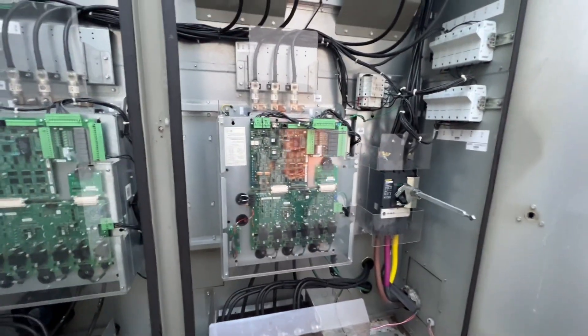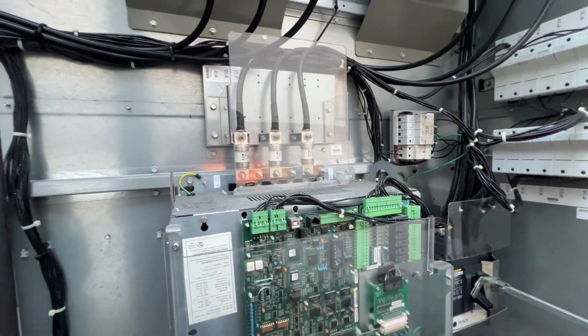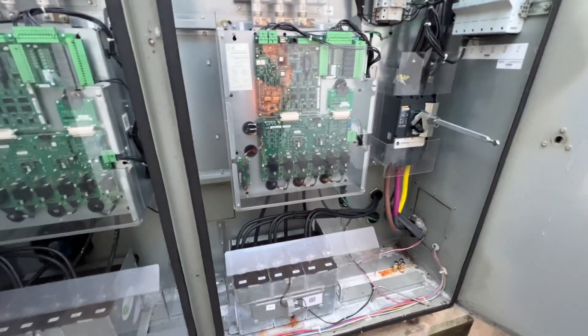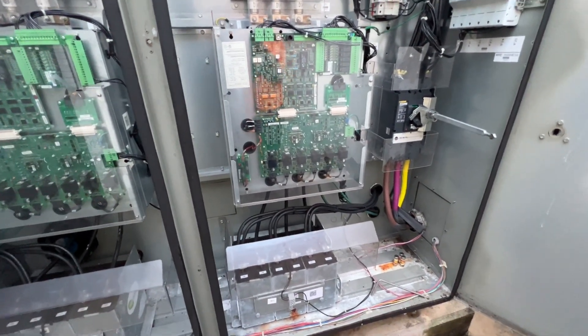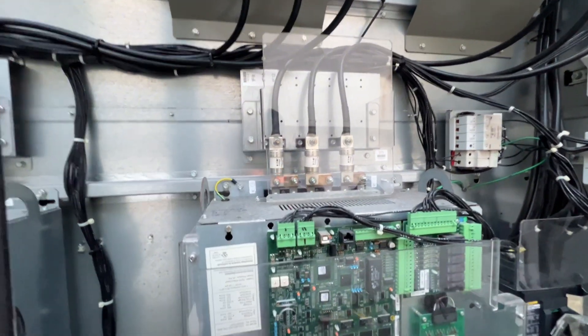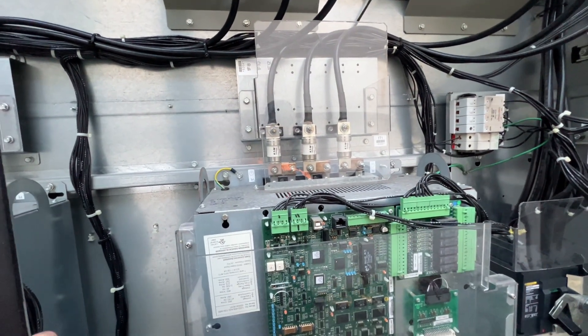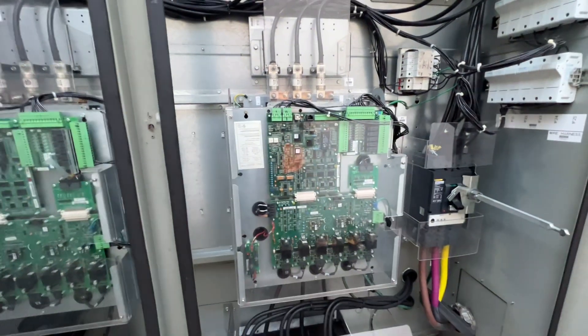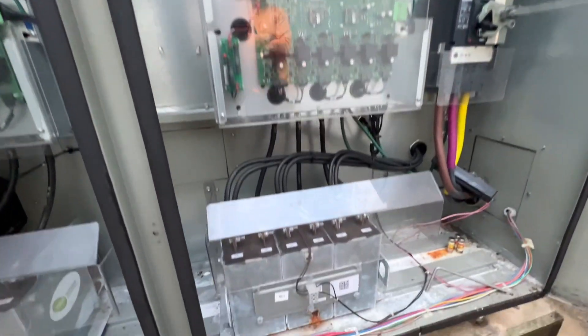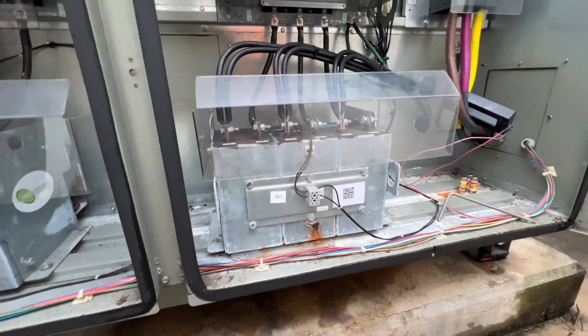So this was our circuit one. In the last video we had two blown fuses — one and three. We're going to swap out all three fuses. We did ohm out the compressor and it checked out fine. We're going to run a megger test on it and verify there's nothing else wrong. This was the one where we found the lizard had shorted across L1, so hopefully that's all that's wrong.